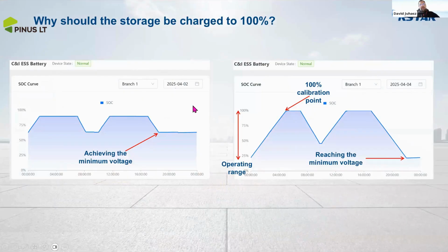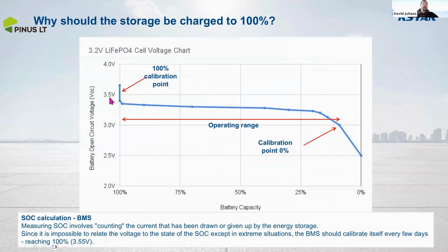The equipment should be charged to 100% every 2 or 3 weeks. It depends on the usage, and we need this because the calibration point is at 100%, and this is 3.5 volt, the maximum cell voltage of each cell. If we reach that 100%, it makes sure that the cells inside the battery have the same cell voltage, and this means that our system has a balanced charge and discharge for the full battery capacity.